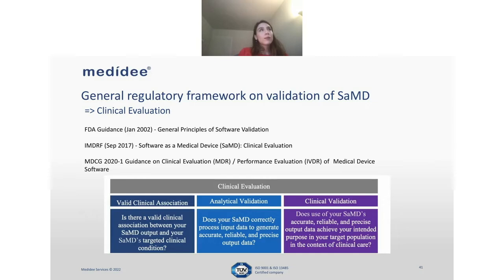And what does this mean? It means that you need to demonstrate the ability of the medical device software to accurately, reliably, and precisely predict the output data based on the input data, like generate an output from the input data. And here, the approach, I think, is rather instinctive. The approach follows verification activities for software. For example, that could mean following the state of the art, e.g. demonstrating that you're compliant with state-of-the-art standards such as IEC 62304, etc. The various verification activities for your software that demonstrate technical performance.